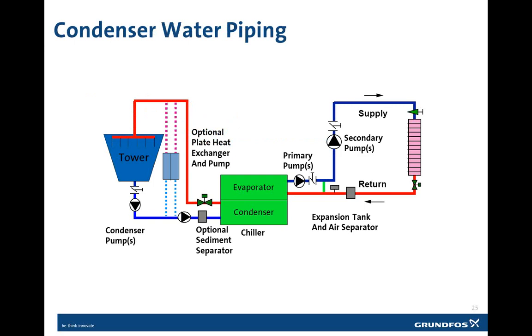With condenser water systems, pumps are required to circulate the water from the chiller condenser to the cooling tower and back. When it's piped in an open system, a filter or a sediment separator is often used. In areas where there's excessive dirt or debris present, a plate heat exchanger with an additional pump is often used. As we can see in this diagram here, we have the tower on the left, and then we have it with the optional plate heat exchanger and pump, and then the sediment separator for the system. That's going to and from our condenser unit, and on the right side is serving our load with our evaporator, with our primary pumps, secondary pumps, into our system, and then expansion and air tank returning back to the system.